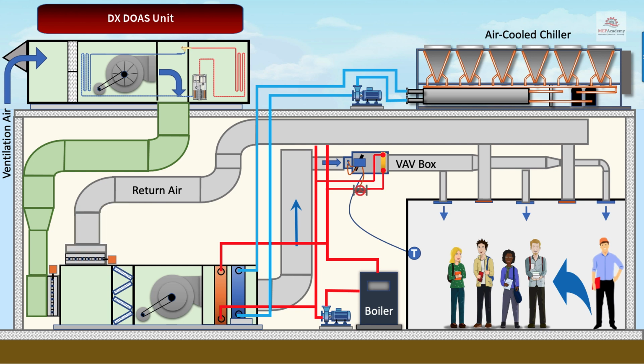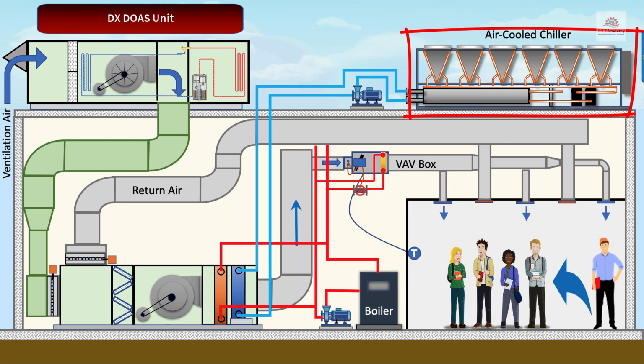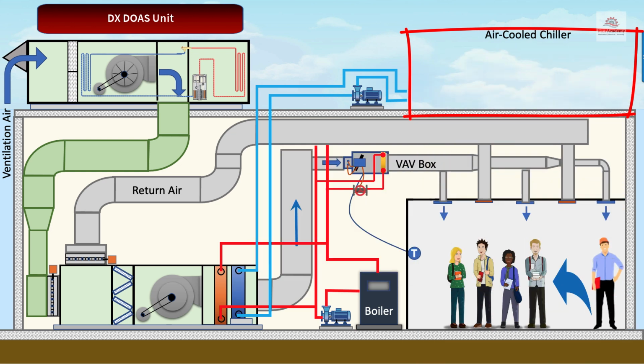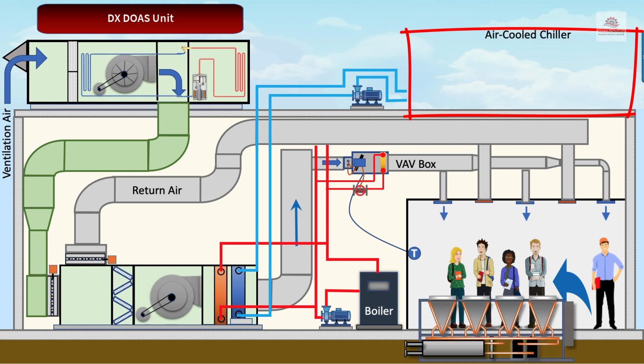Since the dedicated outside air unit is handling all of the load for the ventilation air, the chiller can be reduced in size along with the air handler cooling coil, so we'll remove this large air-cooled chiller and install a smaller one.